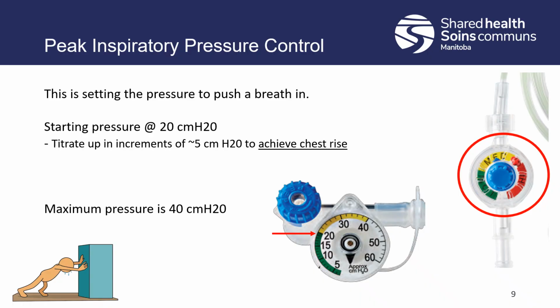So to set the pressures, we want to set the pressure to 20 centimeters of water pressure for our babies. So realistically, we're going to set the dial there, as you can see on the right with the blue dial. We're going to set the little triangle in between the green and the yellow, and that'll get us to about 20 centimeters of water pressure. It does mention that if this isn't working for you, you can titrate it up a bit. So we can just adjust the dial, but make sure you're watching your manometer there, how far you're going, because we don't want to go past 40. That's quite a bit of pressure. So we don't want to be causing barotrauma.